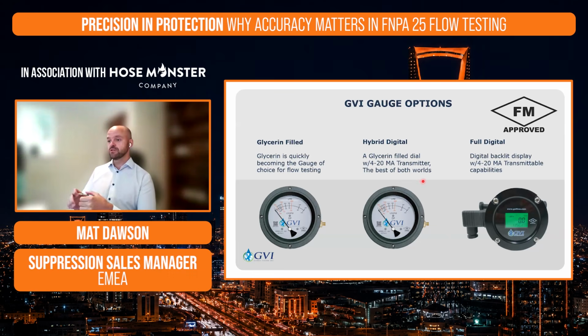We do have other options. So in the middle, we've got our hybrid dial, which is glycerin-filled again. What we have with that is a 4 to 20 milliamp transmitter, which is a hardwired connection, which would go to third-party equipment, fire pump controller, that kind of thing, which gives you the best of both worlds. And then on the right hand side, we've got a full digital option. So it's obviously easy to interpret, as well as that hardwired transmittable option. So yeah, we've got the full suite of options, all FM approved.